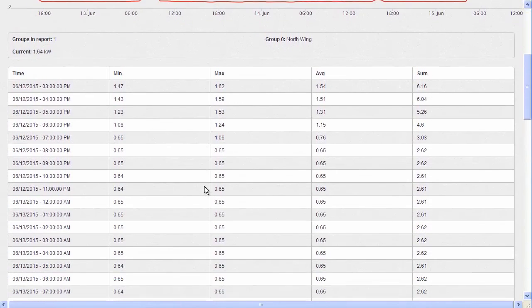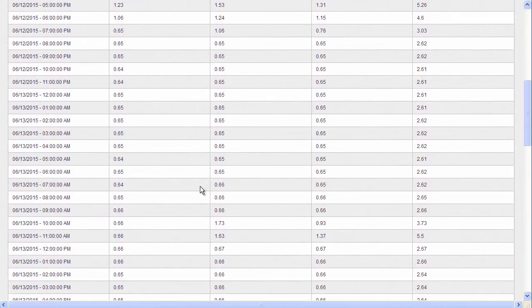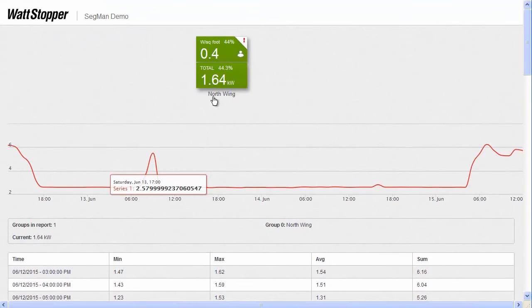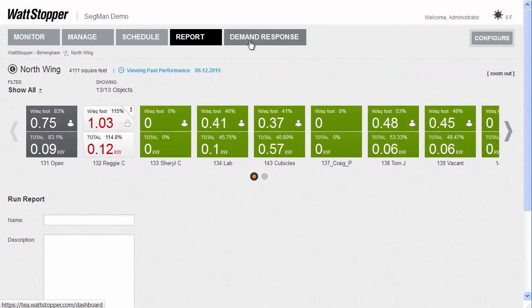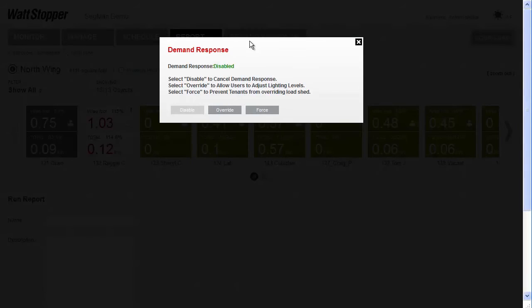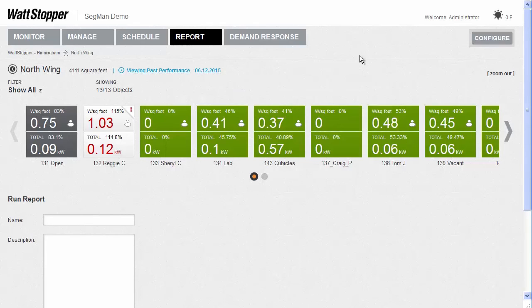The next tab is really exciting. For those of us in California, there's now an energy code requirement that projects larger than 10,000 square feet must have a demand response capability. With the latest version of LMCS, somebody can go in and set individual Shed 2 level parameters for all dimming loads in the building. A Shed 2 level of 65% means that when a demand response command is issued, any load over 65% will reduce down to 65%, but any load at or under 65% will be left alone.